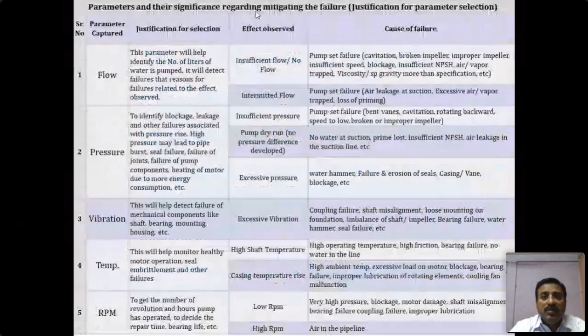Okay. So, parameters and their significance regarding mitigating the failure. The parameters captured are flow, pressure, vibration, temperature, and RPM. What are the effects observed for the flow? Insufficient flow or no flow. What can be the causes for the insufficient flow? Pump set failure, cavitation, broken impeller, improper impeller, insufficient speed, blockage, insufficient NPSH, viscosity. These are the different causes for insufficient flow or no flow. If I talk about intermittent flow, then the possibilities are pump set failure, air leakage at the suction, excessive air or vapor trap, and loss of priming.